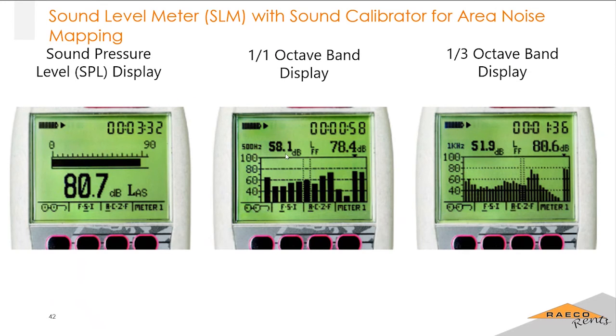Okay. Yeah, here's just a few different pictures of what you could see on the SoundPro. So there's the sound level meter view, or the SPL, which is just basic. It's just giving you your decibel level. Then you have the octave band displays. So there's your 1-to-1 and your 1/3, which shows much more detail. But you can cycle through these views using the 4 soft keys on the instrument. There's 4 black buttons there, and underneath each logo, that's what the button corresponds to. So that little glasses logo is how you can cycle through the different views that you have here.